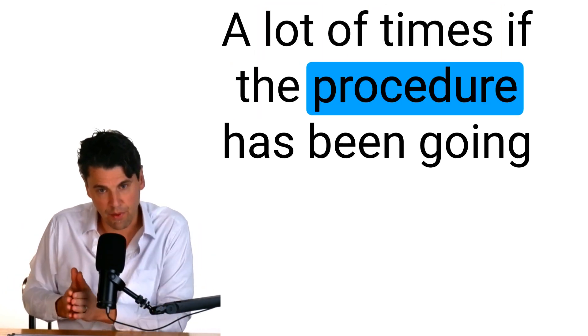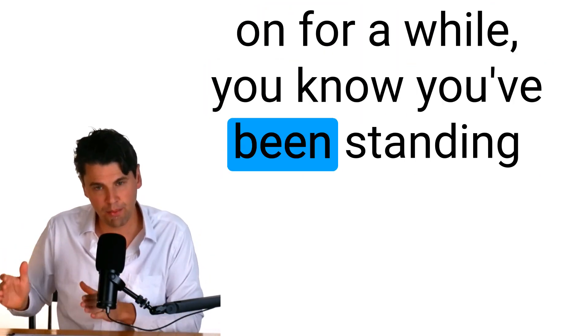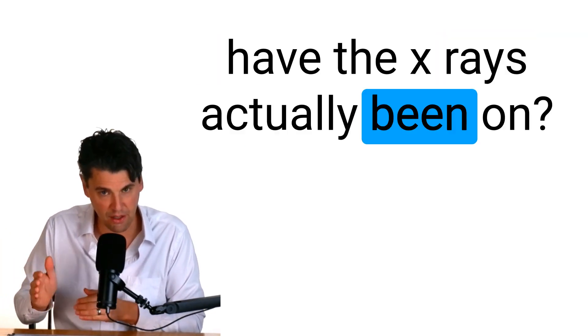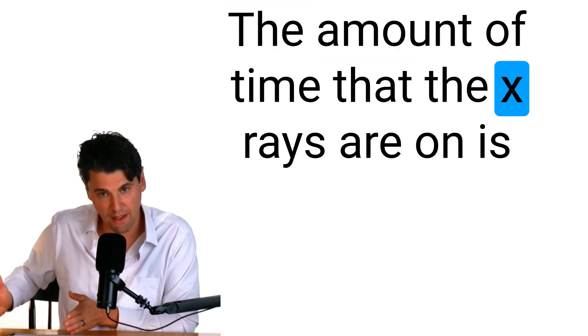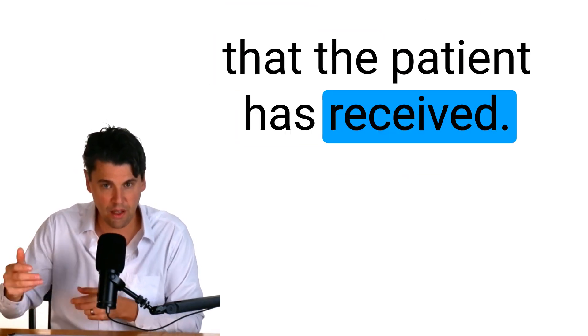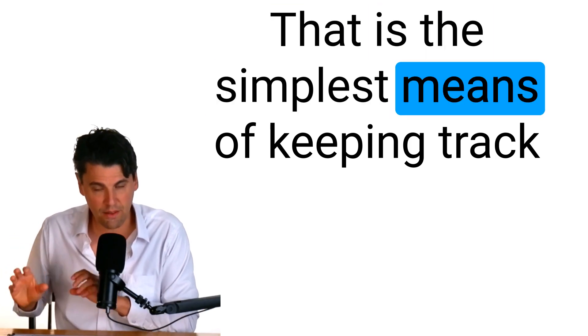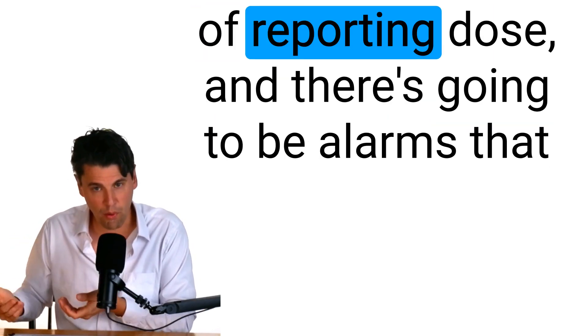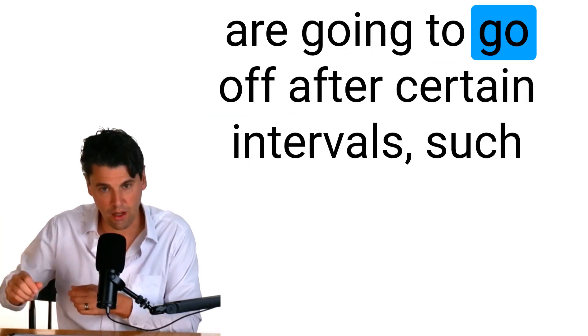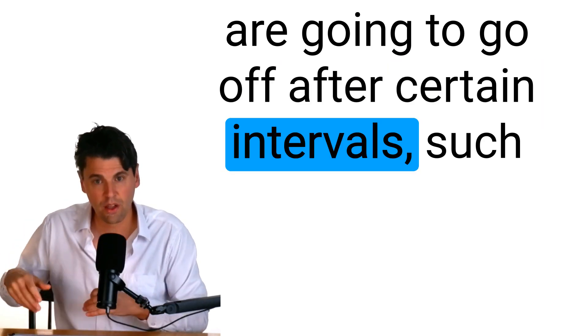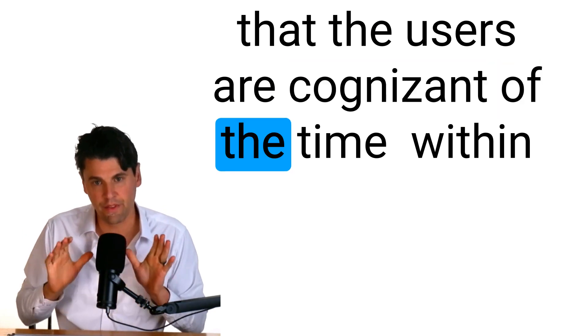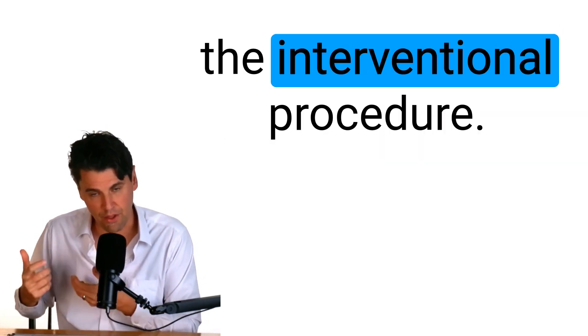A lot of times if the procedure has been going on for a while you know you've been standing there for an hour but how long have the x-rays actually been on. The amount of time that the x-rays are on is going to correlate with the dose that the patient has received. That is the simplest means of keeping track of reporting dose and there's going to be alarms that are going to go off after certain intervals such that the users are cognizant of the time within the interventional procedure.